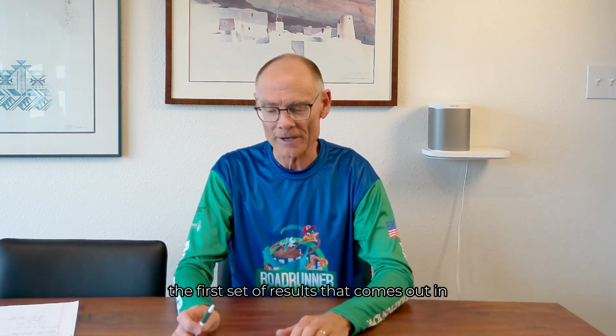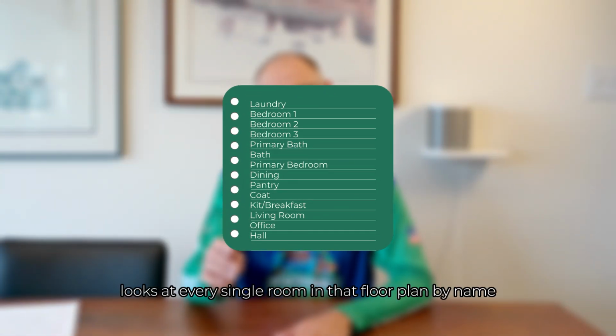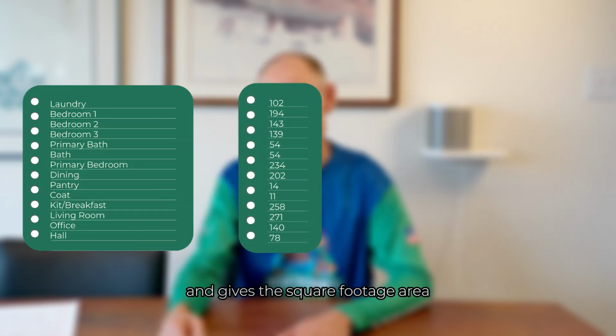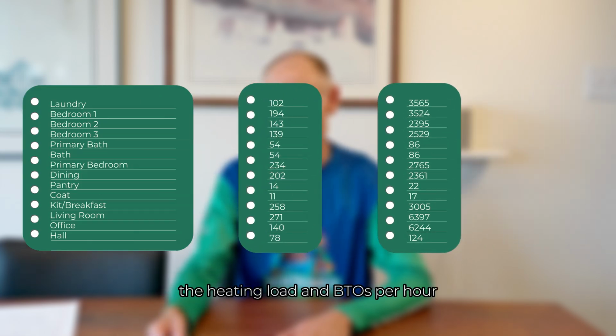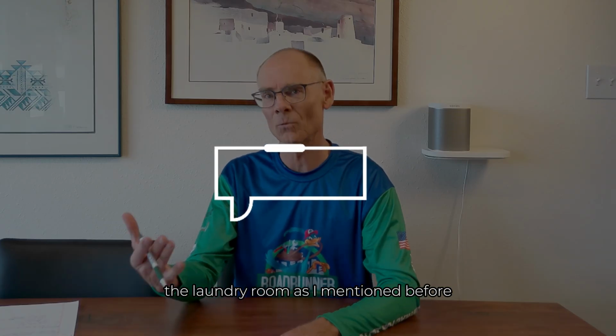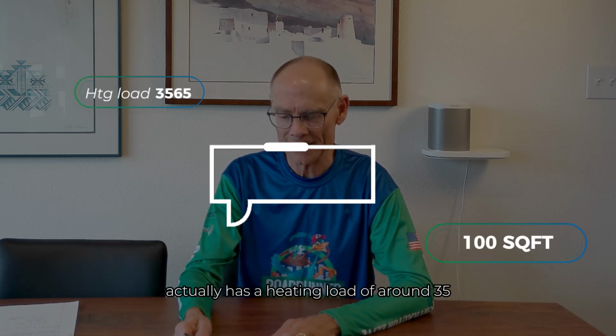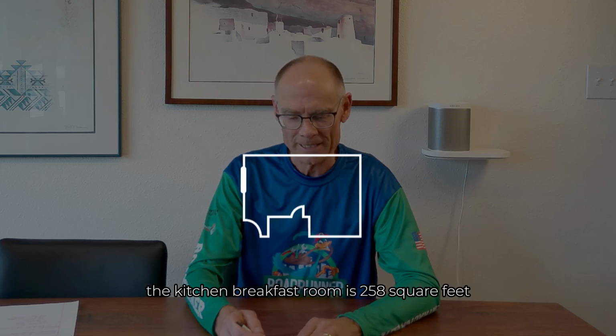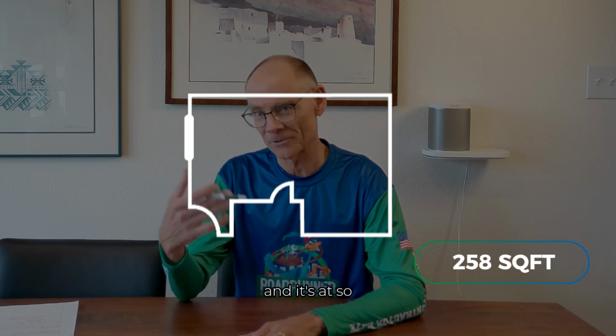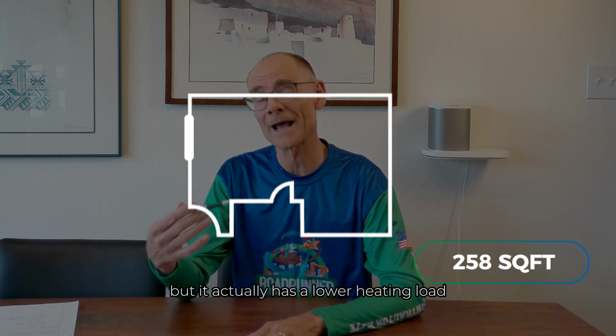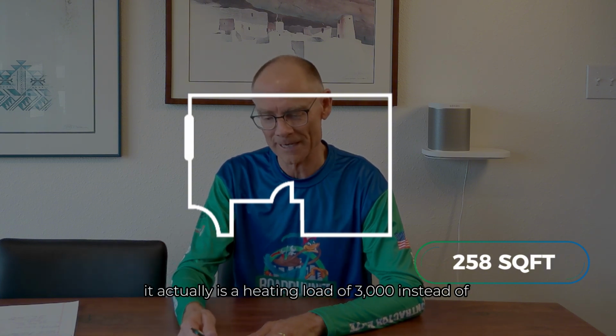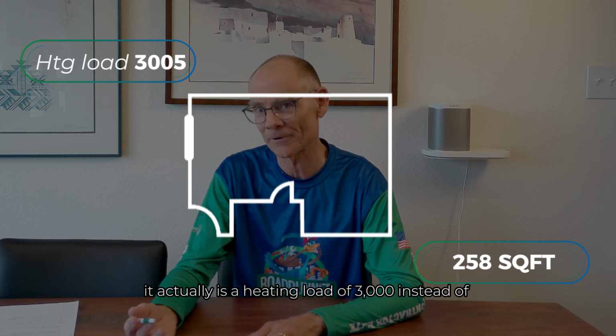So let's look at the results. The first set of results that comes out in the load calculation looks at every single room in that floor plan by name and gives the square footage area, the heating load in BTUs per hour, and then the cooling load in BTUs per hour. The laundry room, as I mentioned before, 100 square feet, actually has a heating load of around 3,500 BTUs per hour. The kitchen breakfast room is 258 square feet, and it's 2.5 times larger than the laundry room, but it actually has a lower heating load. It's a heating load of 3,000 instead of 3,500.